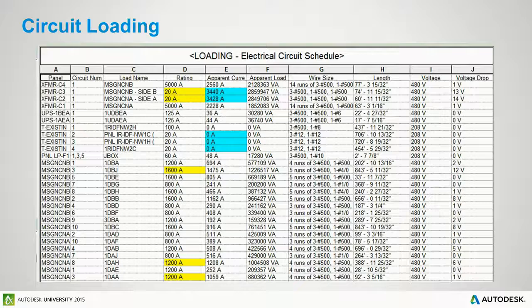But when it comes to wire sizes, you typically can get yourself in trouble very quickly. Because Revit assumes that they're connected in series, Revit is going to start upsizing the wire for the voltage drop. And so you could have a receptacle circuit that would at worst case be number 10s, and you're going to see it jump all the way to number 4s because of the length that Revit thinks it is.